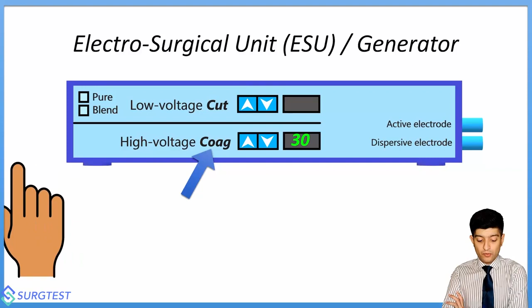Now say I shift the entire cautery to coagulation mode, set to the same power setting of 30 watts. This is the waveform I'm now looking at — very high peaks, but notice the current has actually shut off for a long period in the middle. This coagulating current, so to speak, has a duty cycle of 6%.